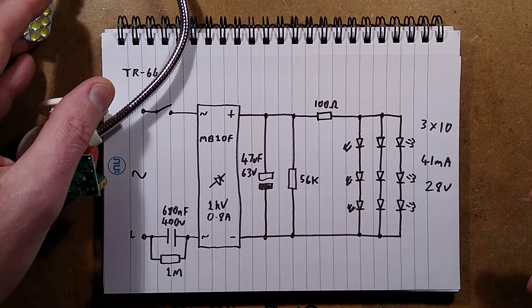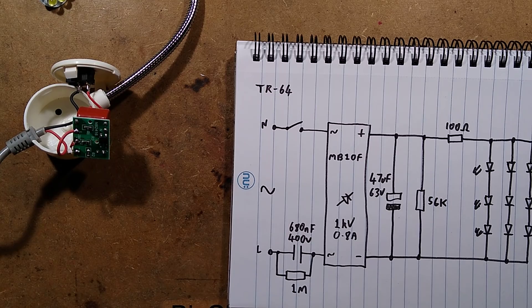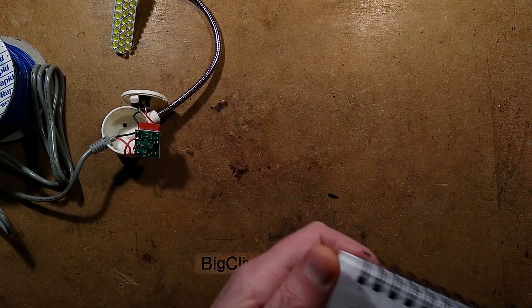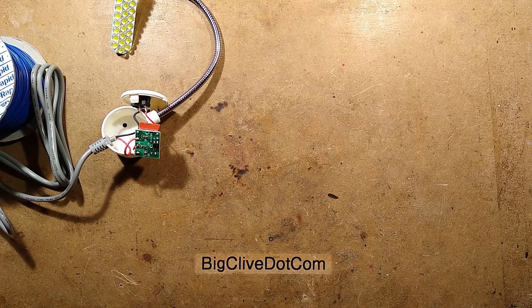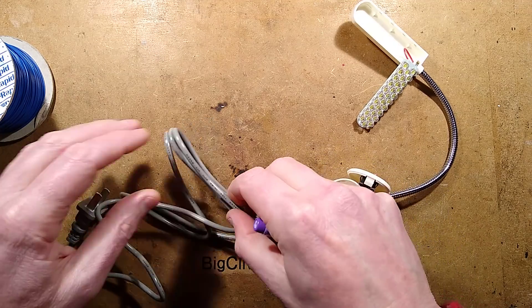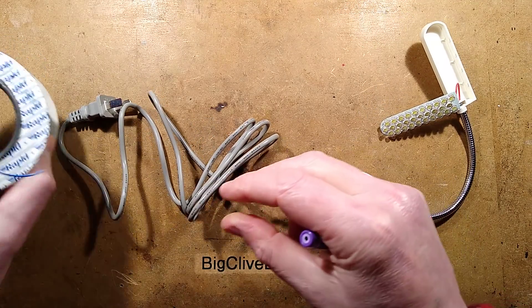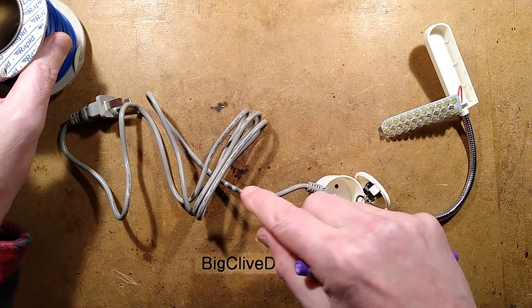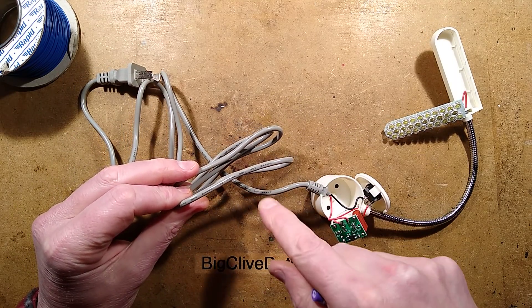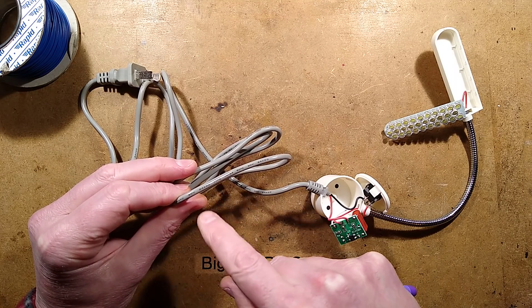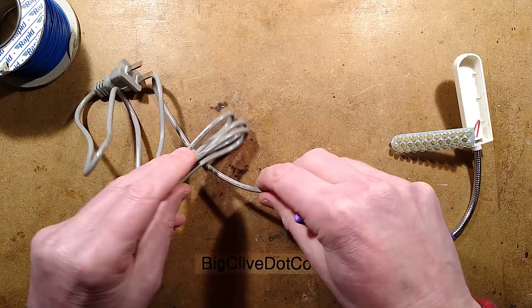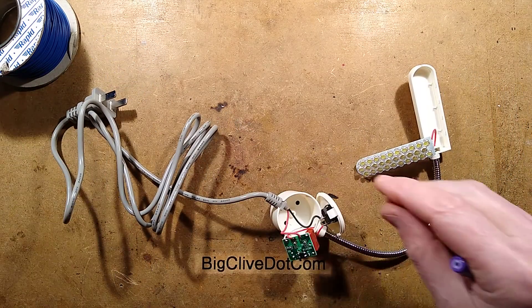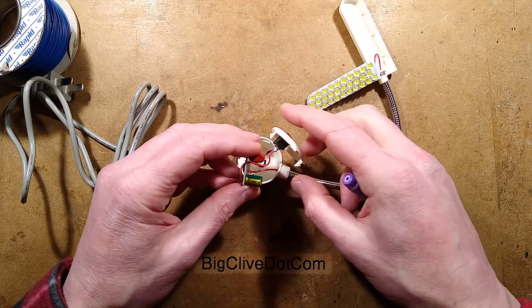I looked up the cable and let's zoom out here. Let's get this out of the way, this little doodle, and brighten the image up just a tad. I looked up the cable. I get the feeling this might be misprinted because it's unusual to see a low rated cable. This stuff I use, it's standard equipment wire, it's rated 1000 volts. I looked up the numbers on this and they all came up 300 volts. So is that 30V just a code or is it just because they've missed out a zero when they were printing it? And maybe they've got a good batch cable cheap because it was misprinted. I don't see a problem with this cable for that application, although the fact it's marked 30 volts will probably upset some people.